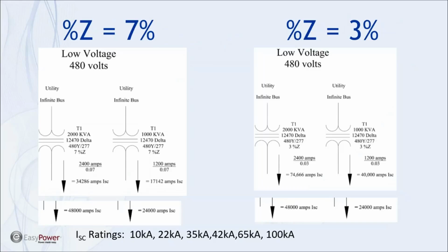the next thing I want to talk about is, well, different transformers may have different percent impedances. Here's a couple of examples where I took the same transformers, and rather than having 5% impedance, both transformers have 7% impedance, which is kind of high in my experience. Sometimes I've run into stuff that was between 6 and 7%.